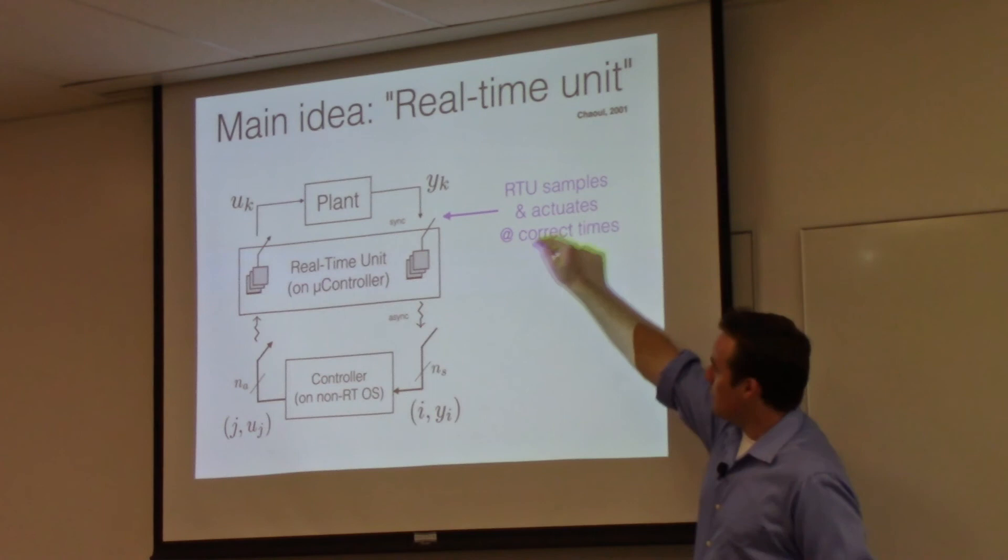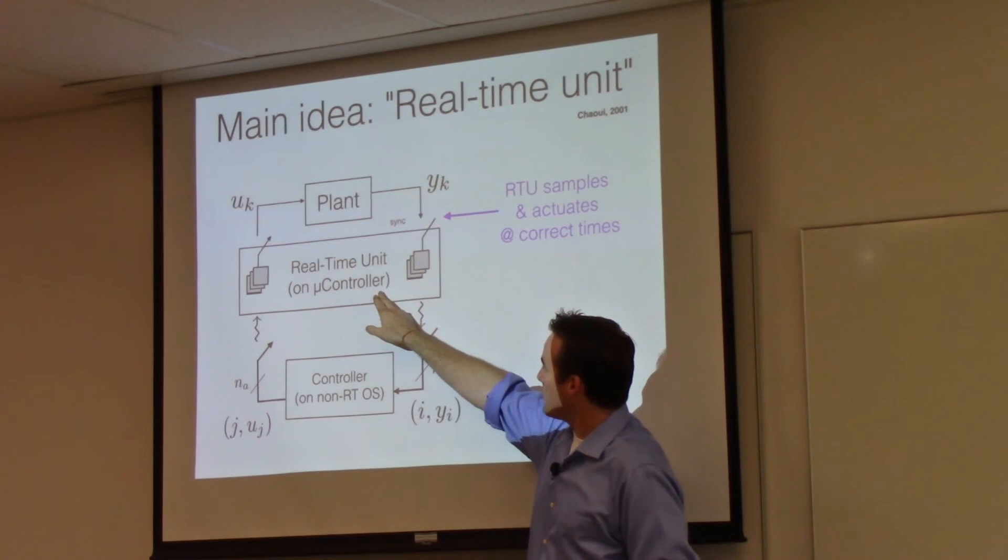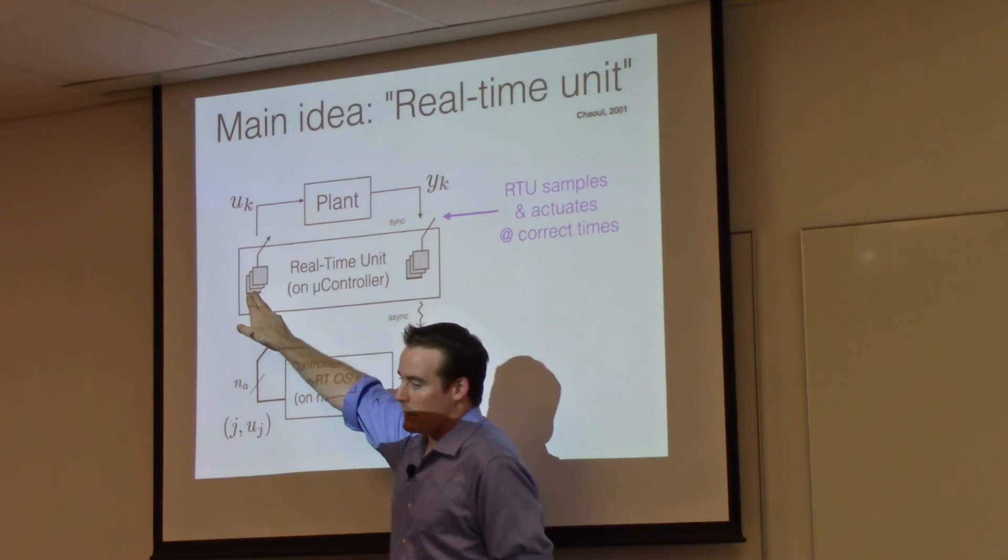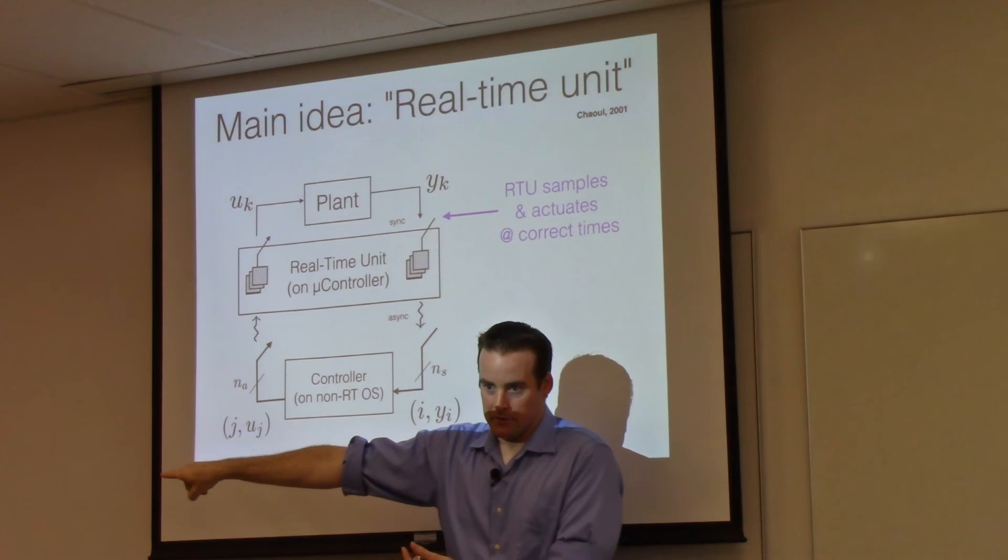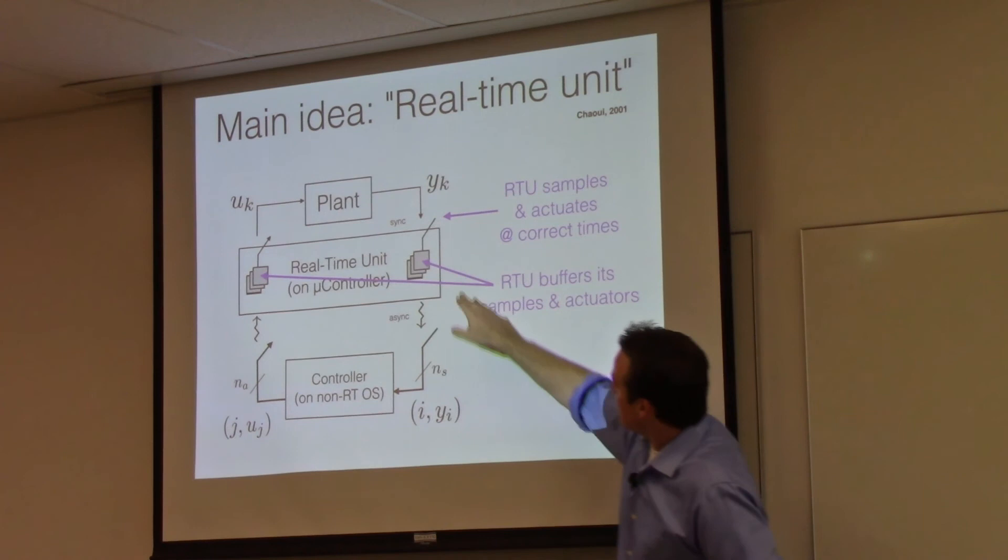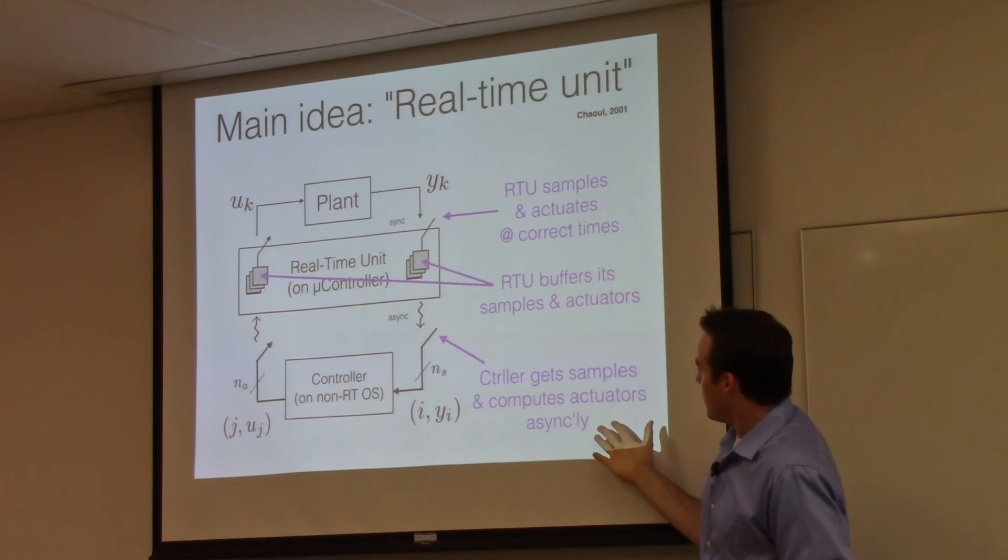The main idea is that the RTU, the real-time unit, will sample the plant periodically at very precise times. This RTU is not doing anything besides just collecting samples from the plant and actuating. It's given an actuation schedule of time-stamped actuator values and at that time-stamp, the RTU will select that sample and write it out to the IO. So that's what the RTU is supposed to do. It buffers up the sensor values and executes out of a buffer the actuator values.